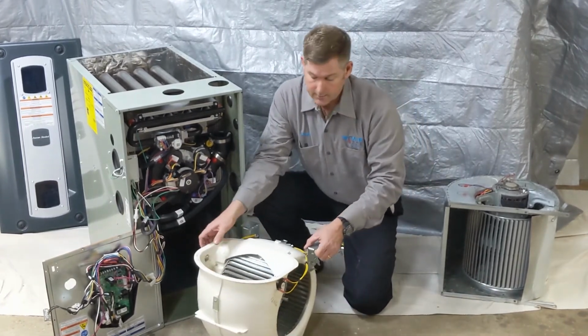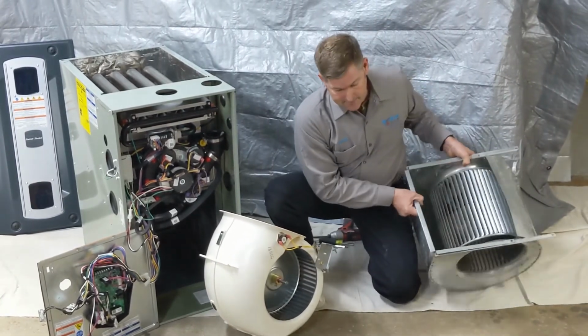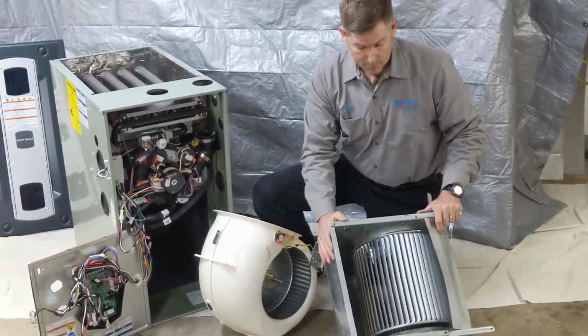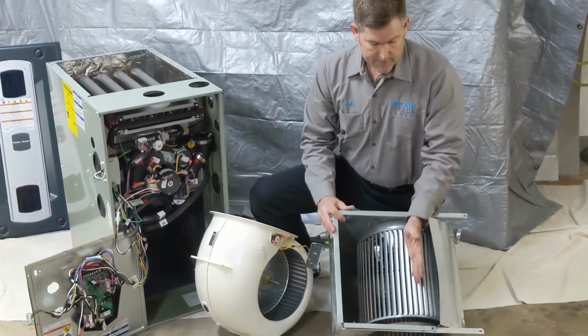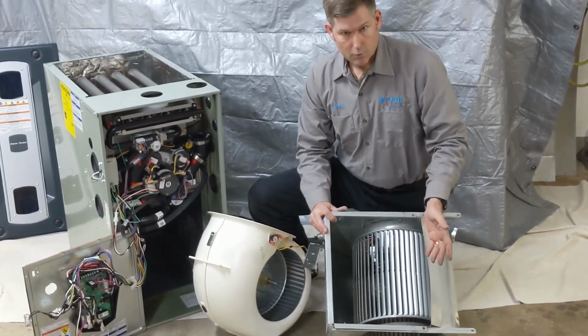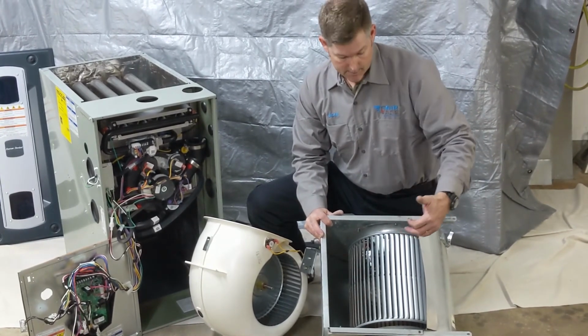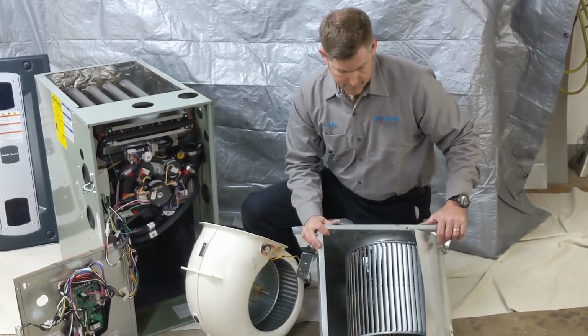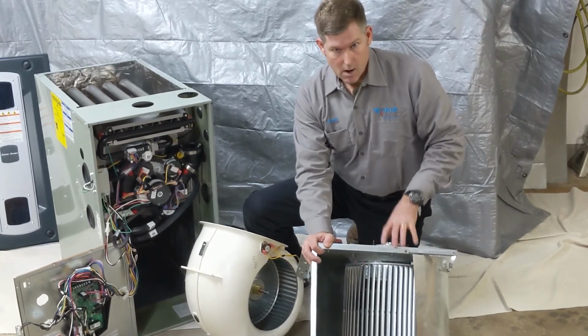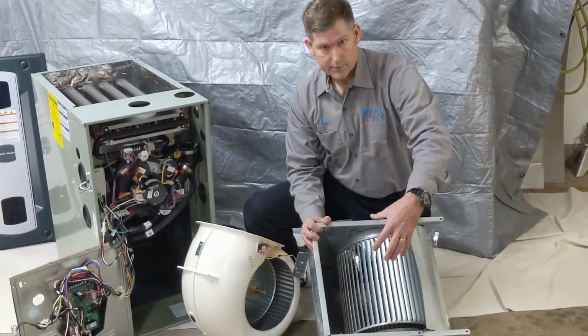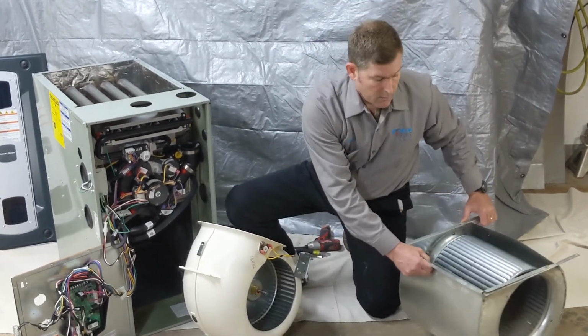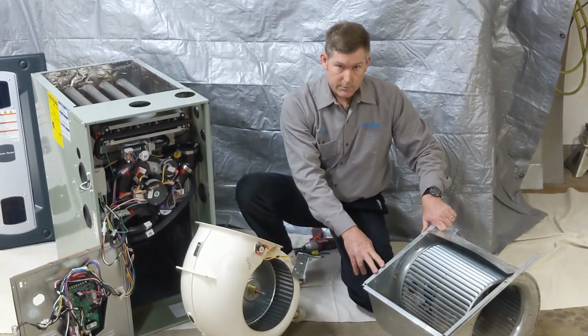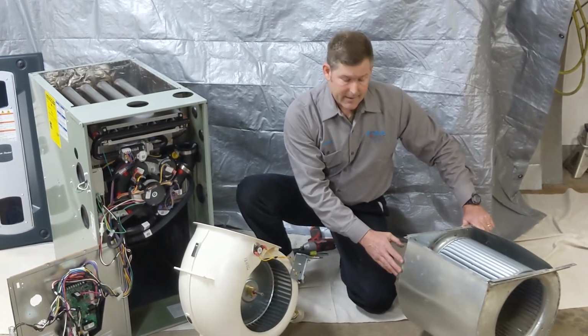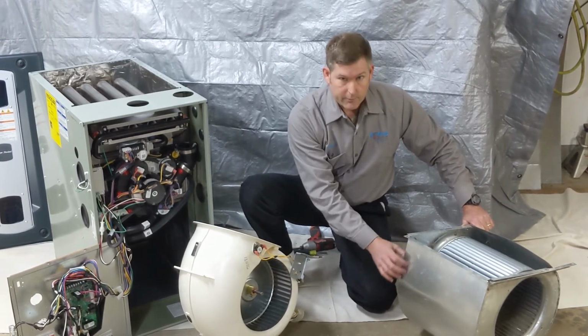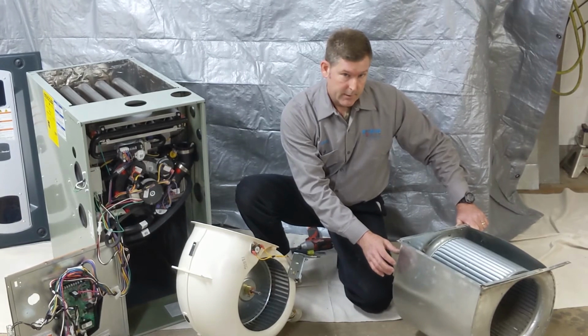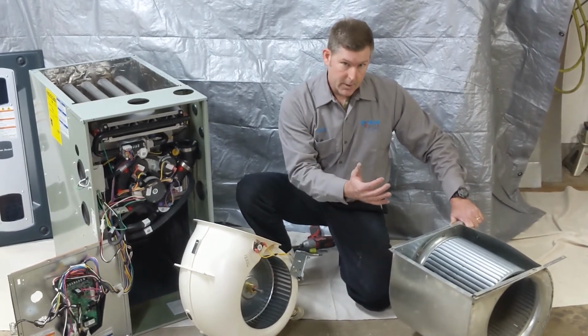Other motor designs, we've got one here that I took out of another furnace. This is typically what you'll find in a conventional furnace blower motor housing. It's sheet metal, which is great, but you get a lot of the fan area exposed. That allows the air to fold around, and not all of it is going up and out into the ductwork. That makes it run longer and decreases your efficiency over time. Also, if you want to service this, you have to take the motor off the housing first and then extract the fan through this opening right here, so it takes much longer to service it. Also, dust really sticks to these metal parts, and it's more of a square design. Yes, this is molded here and rolled, but out here on the corners, it's all square, and it allows air a place to go other than up your ductwork all the time.